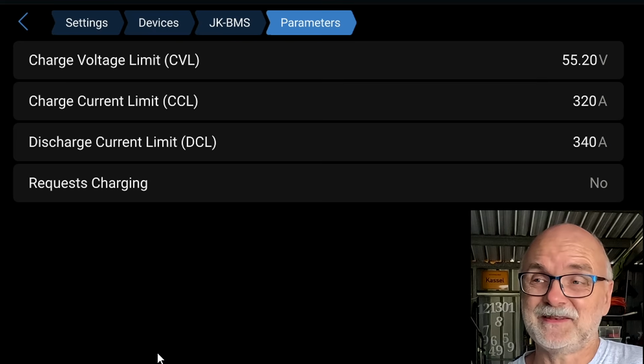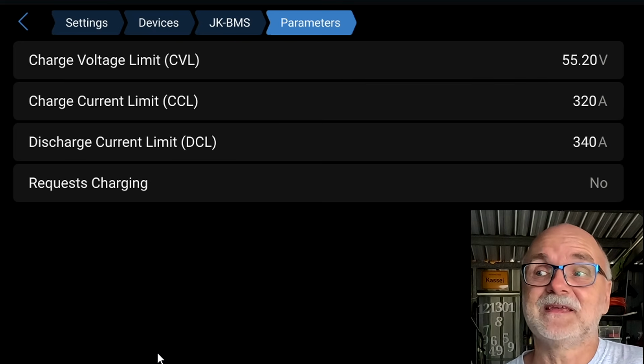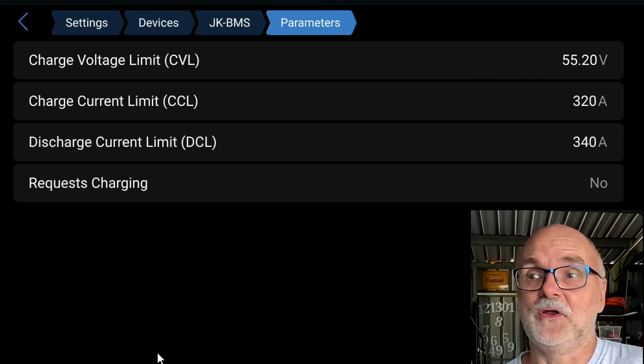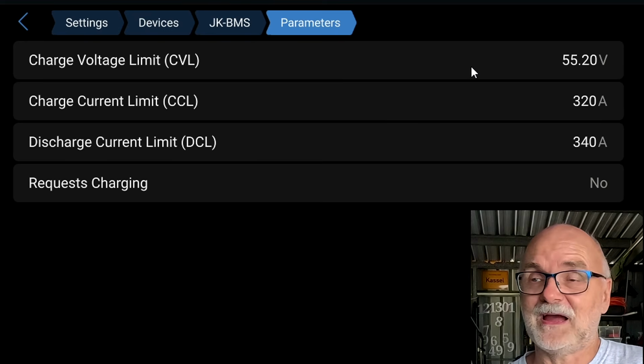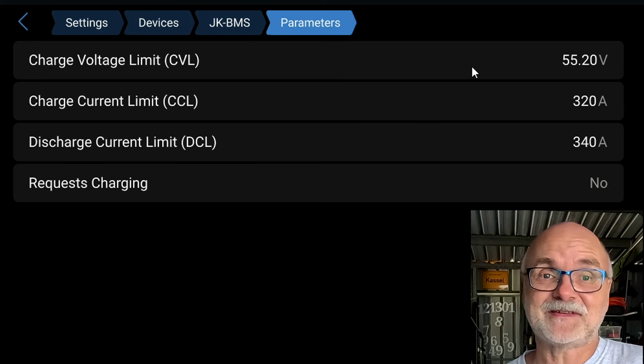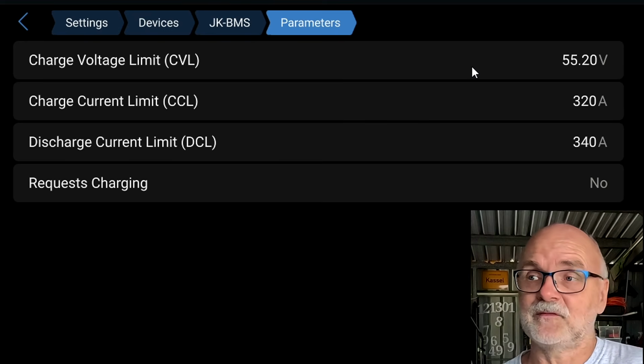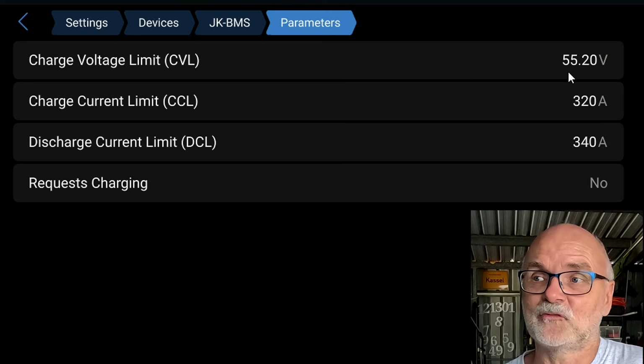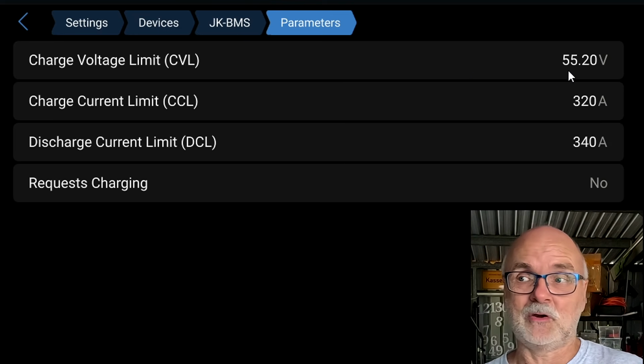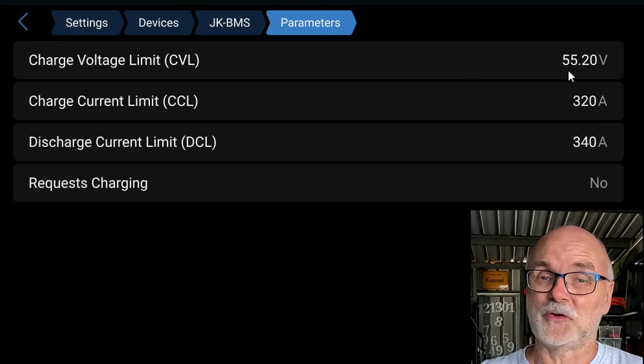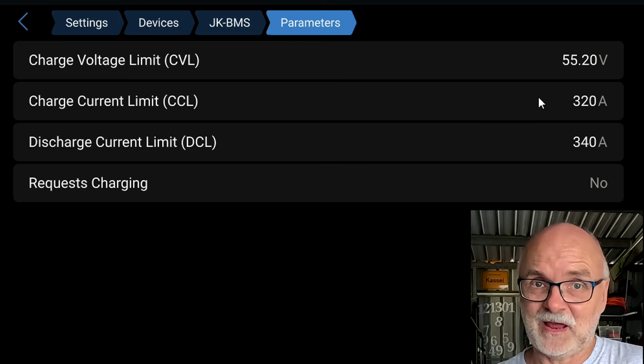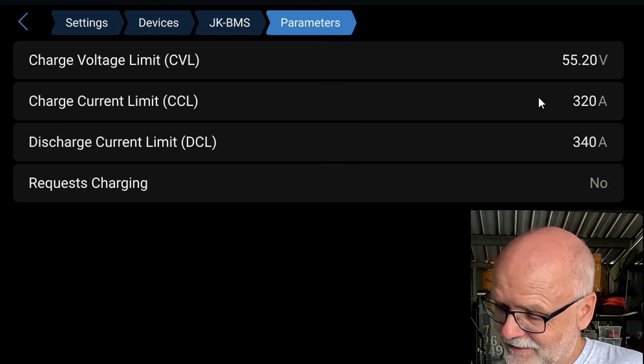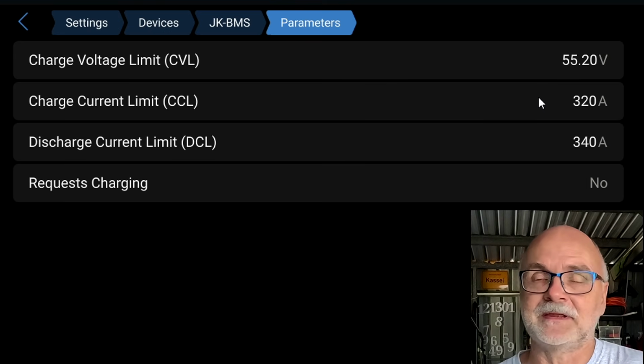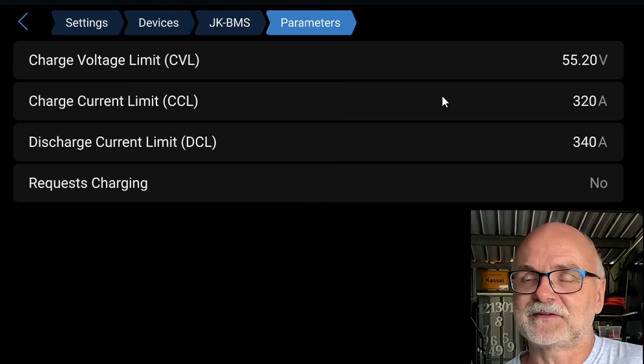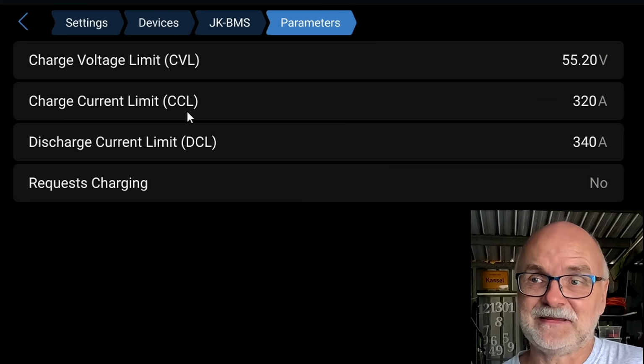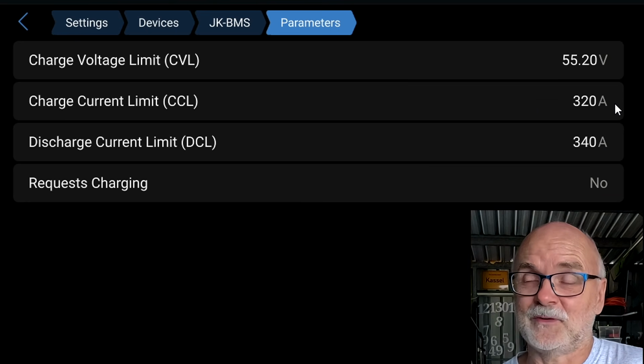These are the charge parameters the BMS, the batteries, are requesting from your inverter. We have set 3.45 as our RCV. This times 16, as we've got 16 cells in each of the batteries, is 55.2 volts. That means your inverter will only charge to 55.2 volts, not any higher. And because we have 4 batteries connected and we have set 100 amps of continuous charge current in the BMS, we've got a requested charge current limit, CCL, of 320 amps.